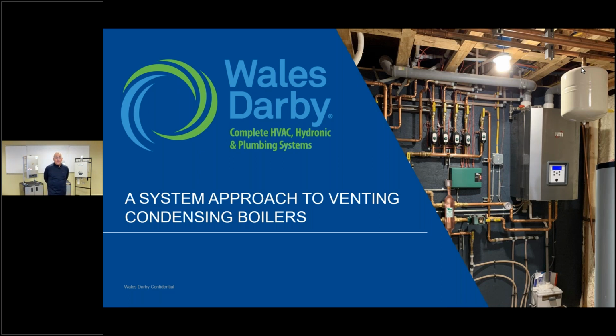Rule number two, always use outdoor air for combustion. Grab that outdoor air. Don't attempt to use room air. A lot of homes get a condensing appliance that's 199,000 BTUs, because a lot of them are doing domestic hot water. And at 199,000 BTUs, Rob, we need 2.5 tractor trailers of free airspace within that area for proper combustion. We're not going to get that in somebody's home, all right? We're not even going to get that in a lot of commercial mechanical rooms because of all the product that is in there.